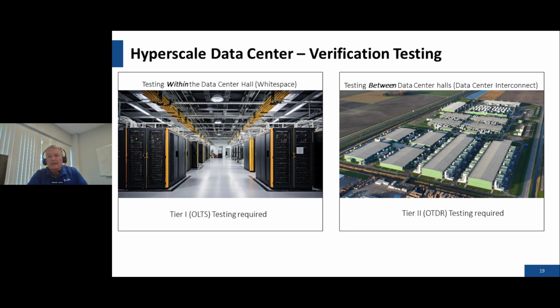And then between data halls, what we typically see being used is a tier two tester, or an OTDR, which will test not only the link itself, but if there are any high loss events along the way, it will actually isolate and locate those. In the picture here, we see very closely spaced, adjacent data halls. In reality, some of these could be several kilometers away where you may have an intermediate splice point or some connectors. So the ability to capture and document the full end-to-end path becomes a lot more critical when looking at these data center interconnect links.